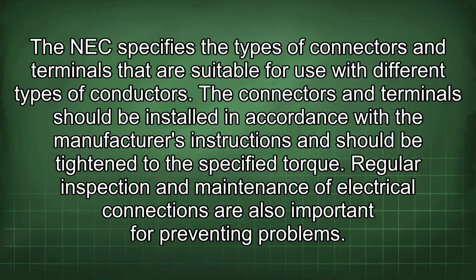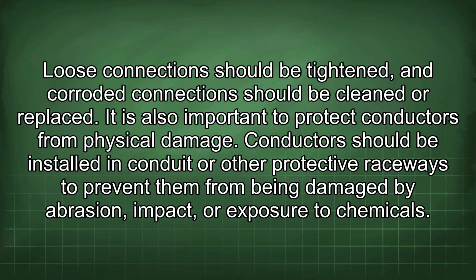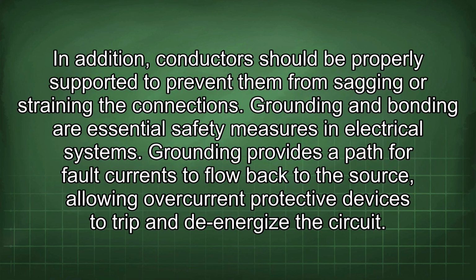The connectors and terminals should be installed in accordance with the manufacturer's instructions and should be tightened to the specified torque. Regular inspection and maintenance of electrical connections are also important for preventing problems. Loose connections should be tightened, and corroded connections should be cleaned or replaced. It is also important to protect conductors from physical damage. Conductors should be installed in conduit or other protective raceways to prevent them from being damaged by abrasion, impact, or exposure to chemicals. In addition, conductors should be properly supported to prevent them from sagging or straining the connections.